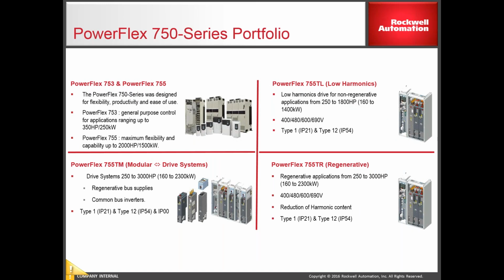So there's 3 flavors of the 755T. The first is the 755TL, which is low harmonic. So this drive is going to meet IEEE 519. So if you've got an application where that's a requirement, you don't have to. In the past, like with the 755, if you had that requirement, you'd have to put in the 18 pulse transformer or something like that. But with this drive, it's got an active front end, and it's got a filter already built into it. So it's going to meet IEEE 519.